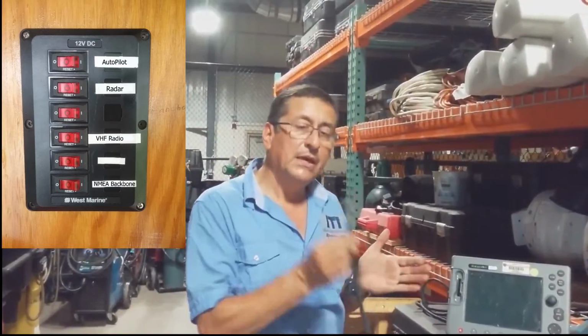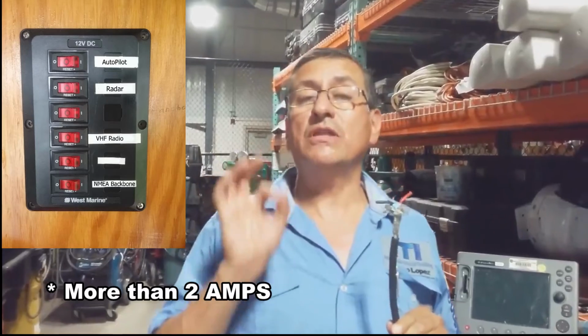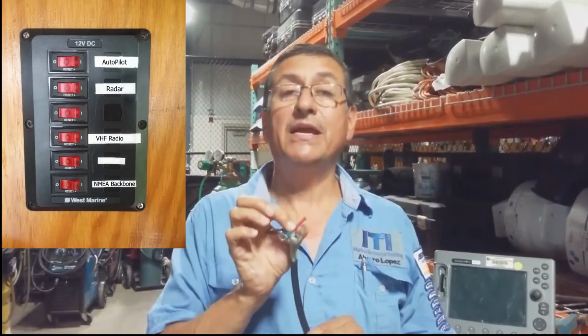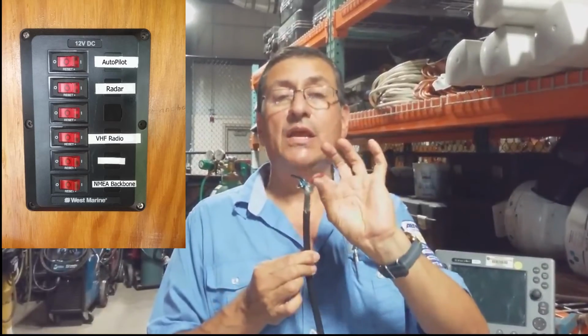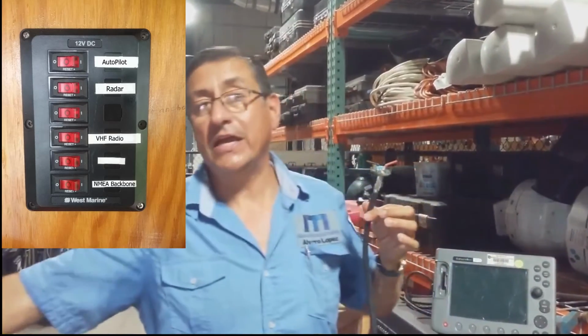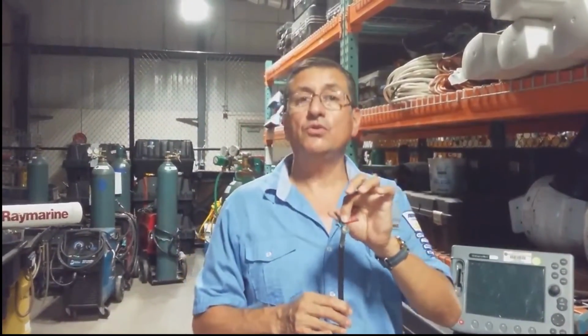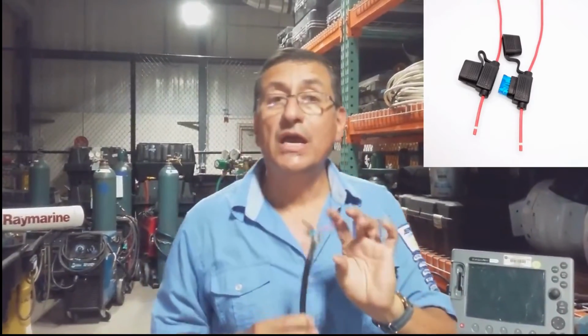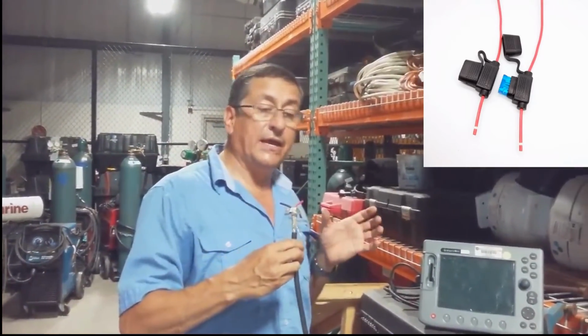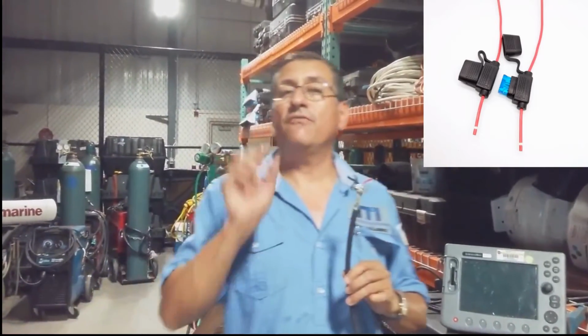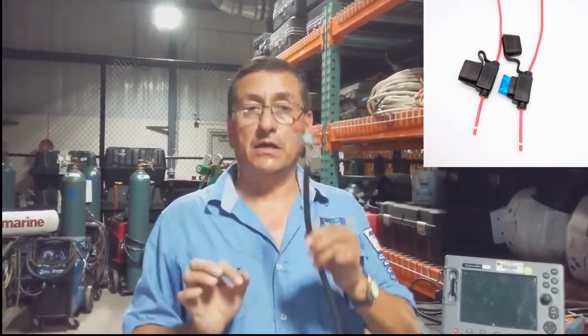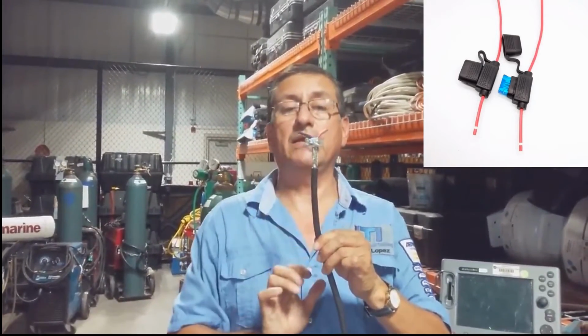Be careful, because depending on the manufacturer, the consumption of this equipment is more than 5 amps. Be careful with the breaker for the radar, because the breaker should be properly calculated according to the gauge of the wire and the distance of the cable. You remember the formula that we use, or the table in the ABYC study guide? Okay, we are going to use that formula and install a fuse. A fuse before the power enters the unit. Be careful. You need a fuse and a properly sized breaker on the cable terminal.